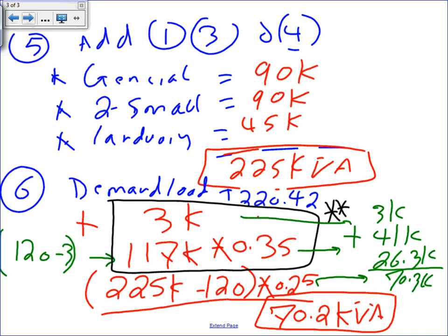So the 3 that we take off at the very beginning, we add that to the total. Yep. The 3 that you take and put aside, it says at 100%, guys. We put it aside just not to derate it. That's the reason why we put it aside. We did not throw it. We just put it aside so we don't apply the derating factor on it.